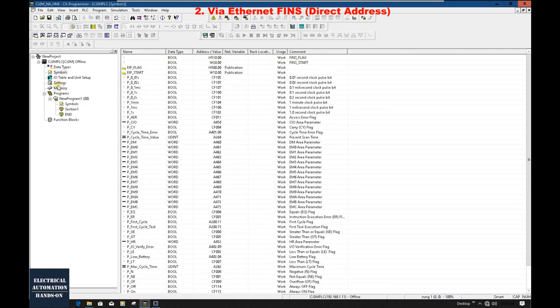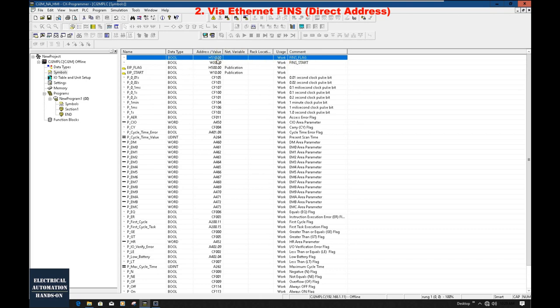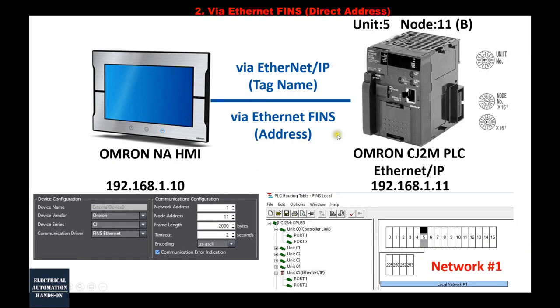That's why most CX Programmer users prefer using W or H addresses with comments rather than tag names. So if your project doesn't use tag names — just comments — all the tags in the existing project have no name, only the absolute address. In this scenario, if you want to use the NA HMI with absolute address connection, you have to use FINS. The FINS protocol supports absolute addresses directly.